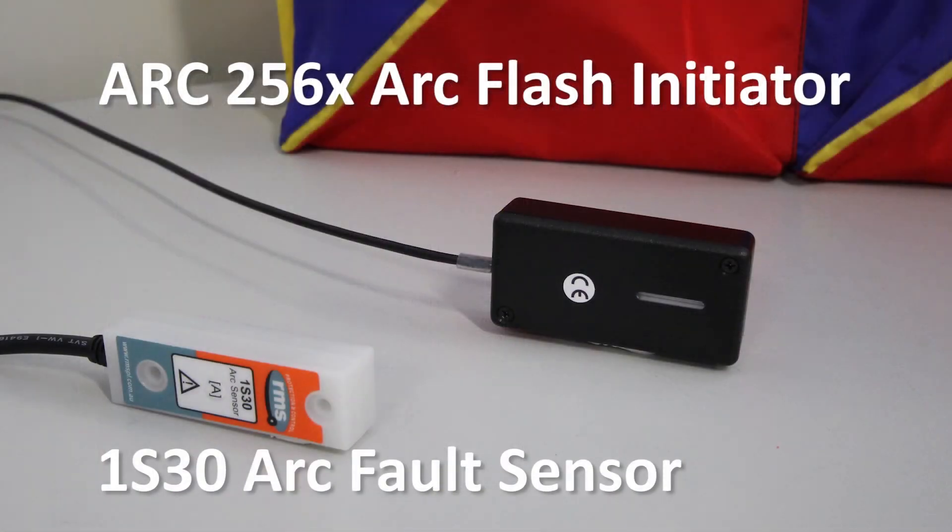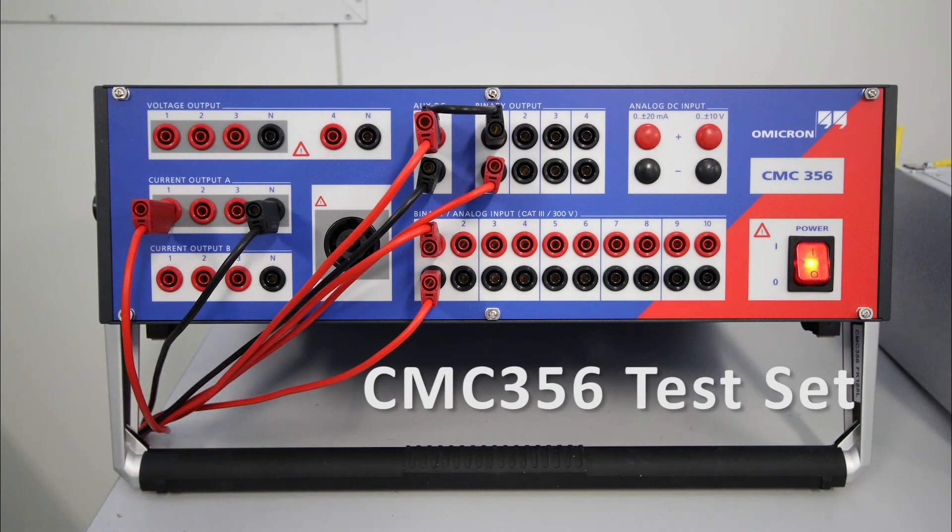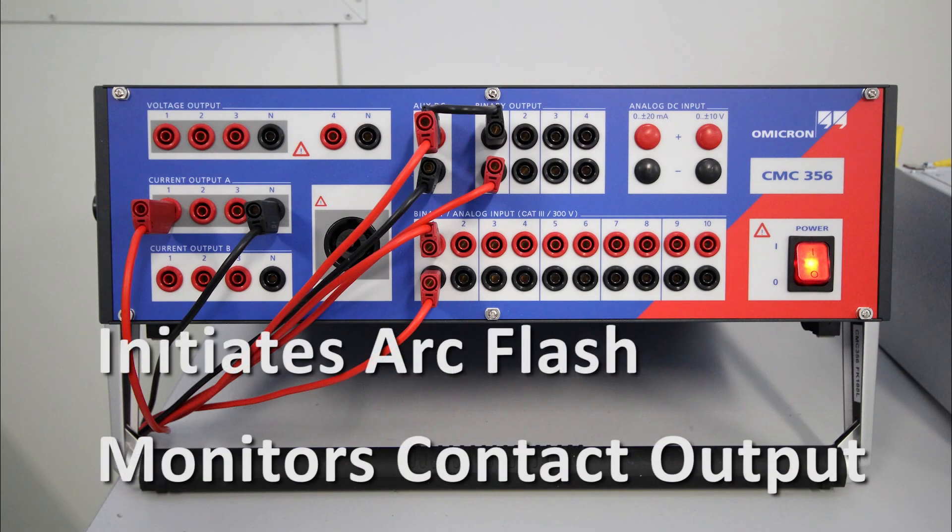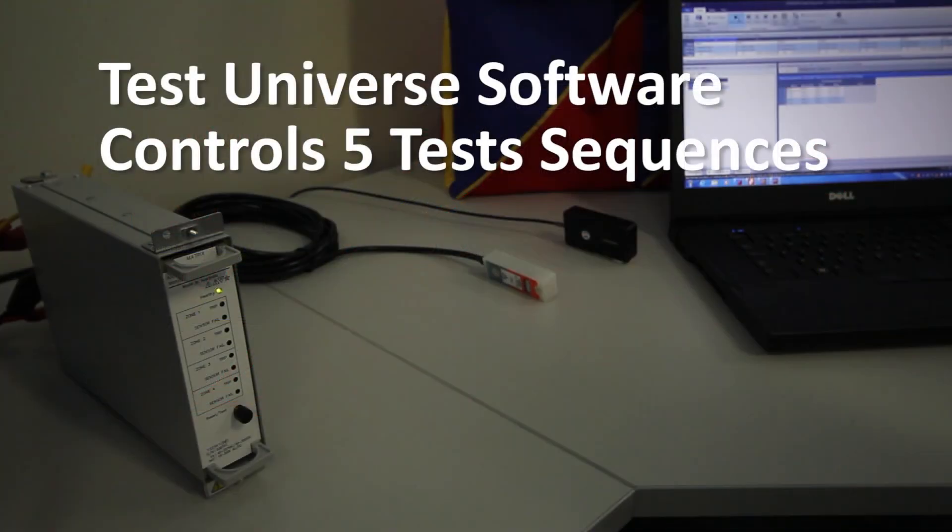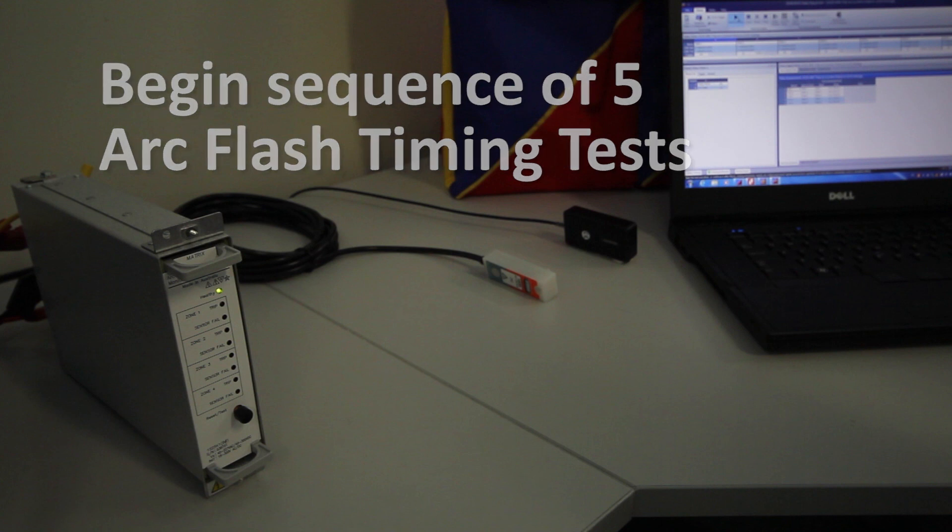The Omicron test set will initiate an arc flash and record the end-to-end operate time. Our test sequence comprises of 5 arc flash tests which are tabulated automatically by the software.